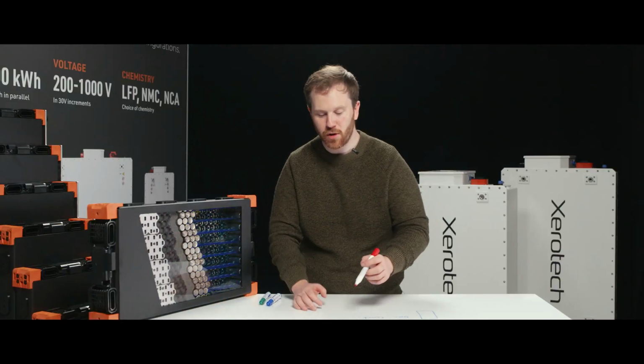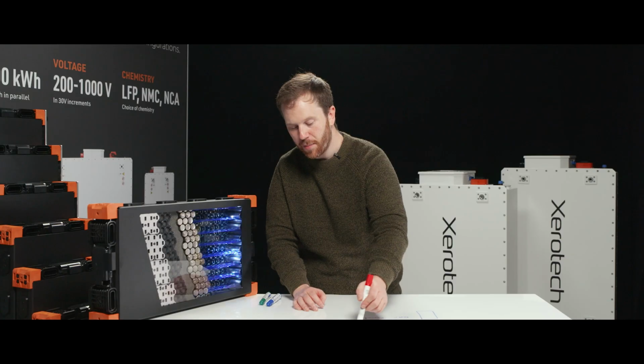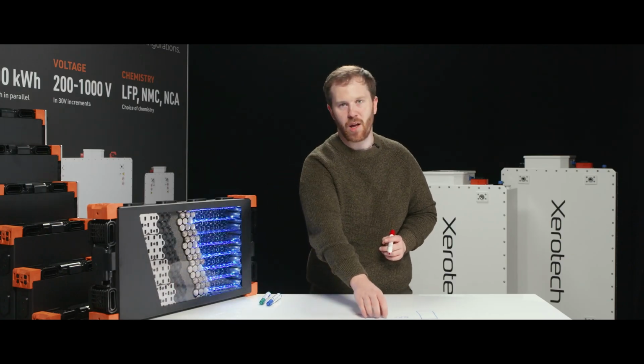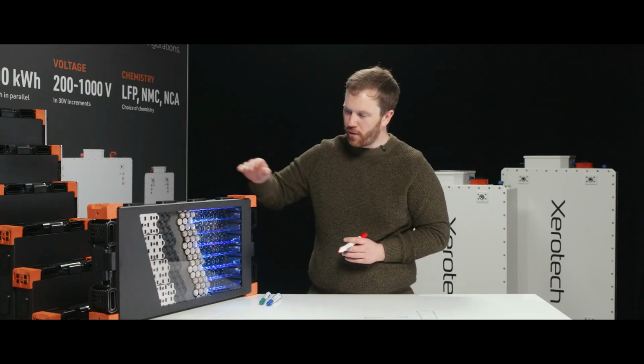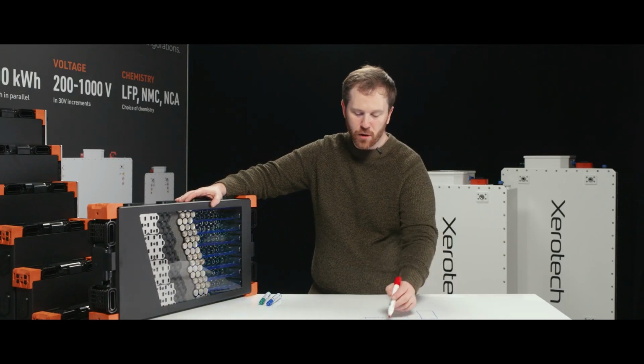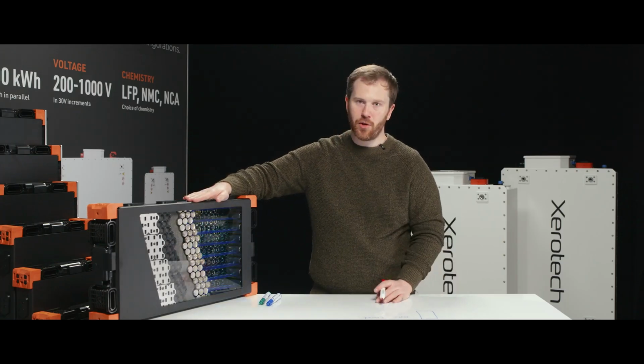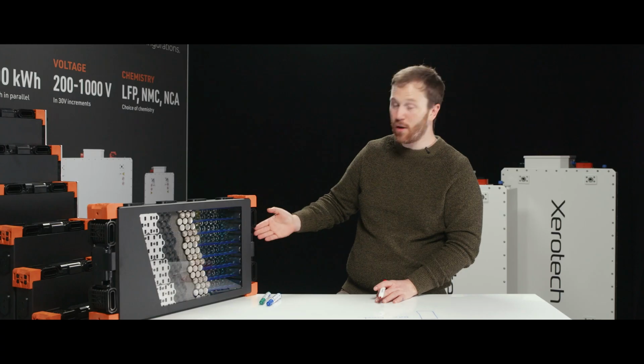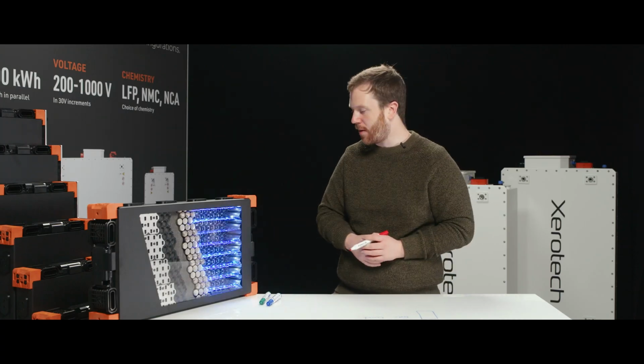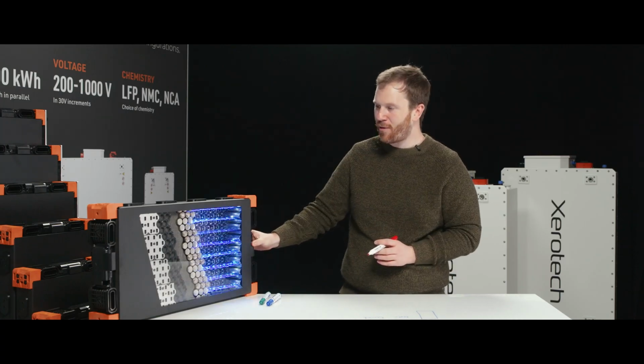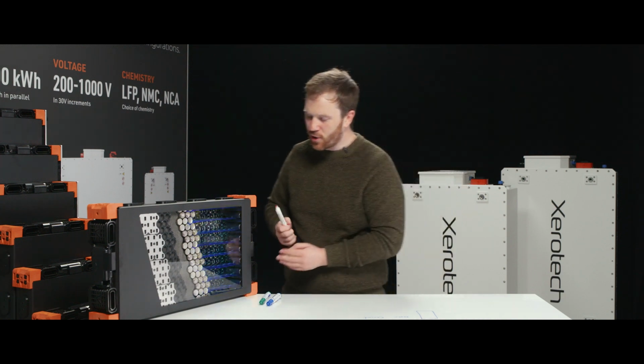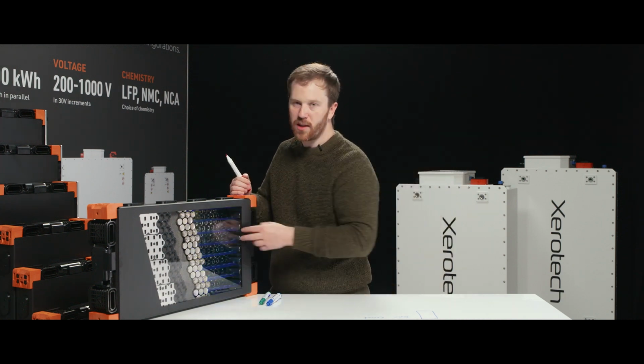If you overcharge too aggressively, you'll breach the upper limit. So you've got to be careful with that current measurement. When it comes to battery modules, we measure the voltage and the temperature at a module level. So for example, in a Xerotech module, but virtually every other battery module, they might have a battery management system here that's measuring the voltage of each cell group.